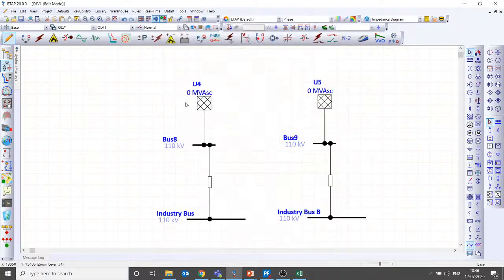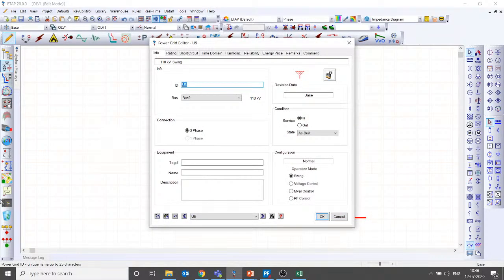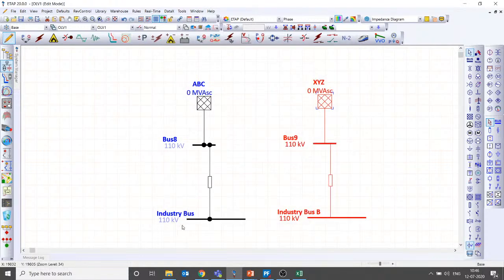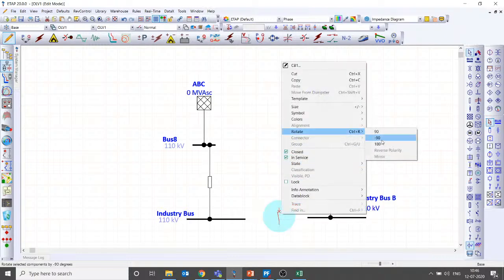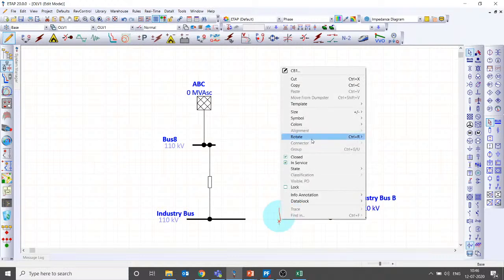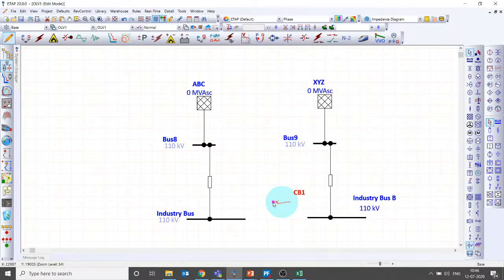So if this is coming from grid A, say for example ABC, from some location, and if this is coming from say XYZ, a different location, shall I parallel these two different grids at my industry substation? Is it possible to connect these two? We may think yes, it is possible, but that results in a huge uncontrolled power flow via your industry bus. So let me run a load flow.